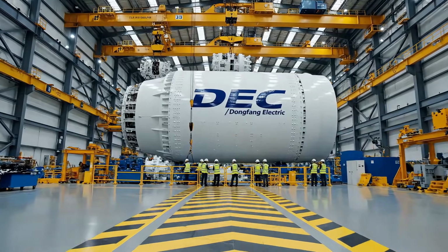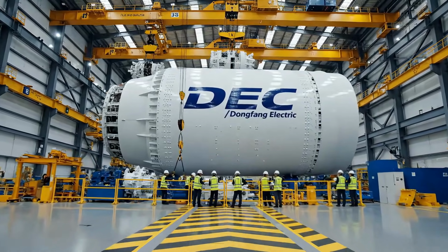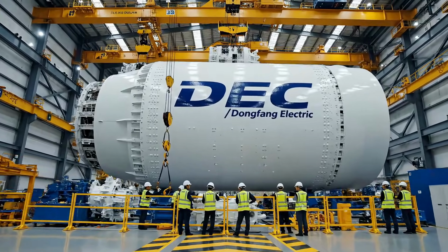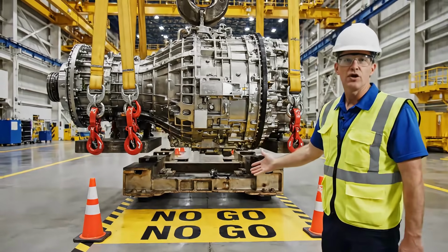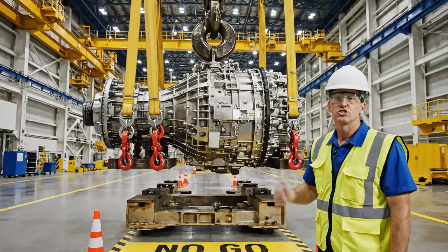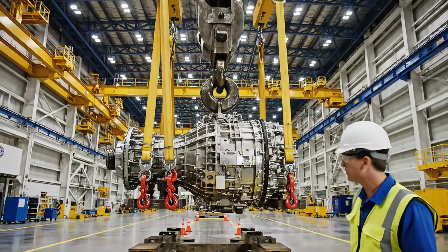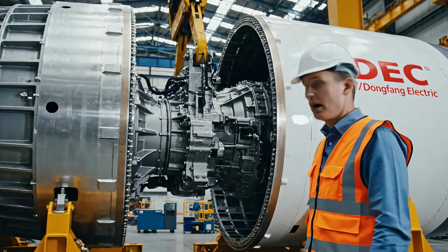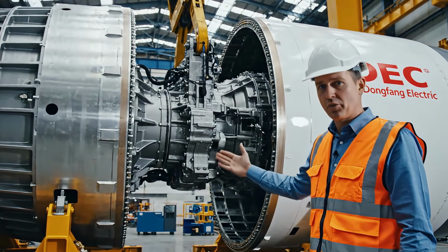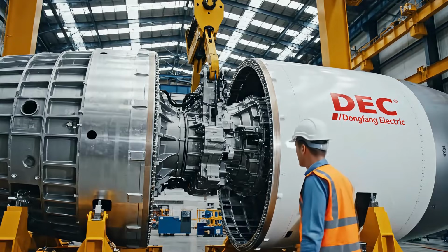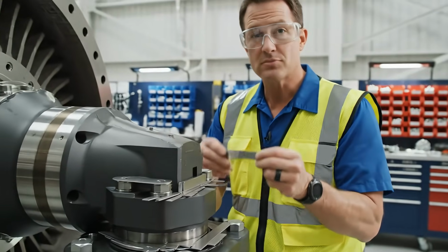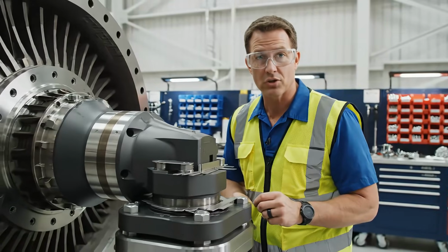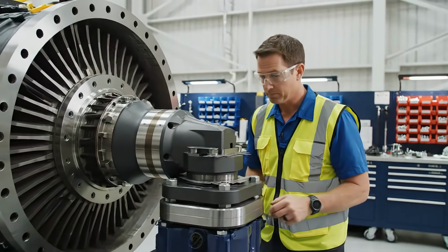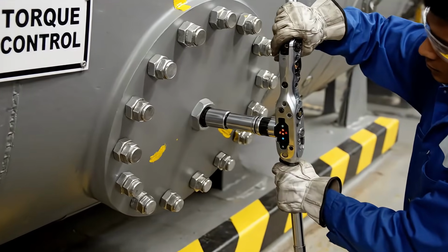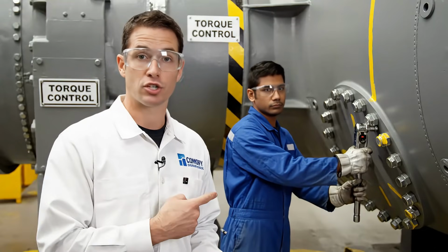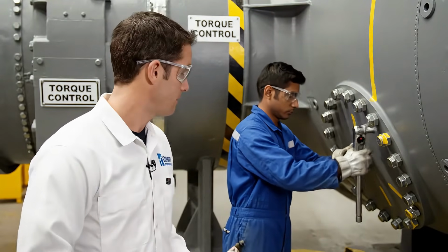This is integration. Mechanical muscle, electrical power, and control intelligence become one machine. We treat every critical module like surgical equipment. Slow, verified, and controlled. Millimeters here decide pressure and vibration. Shims look small, but they lock the geometry of a 26 megawatt drivetrain. Torque isn't a feeling, it's a controlled value, verified and marked.